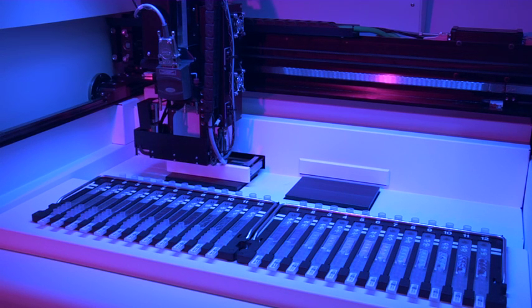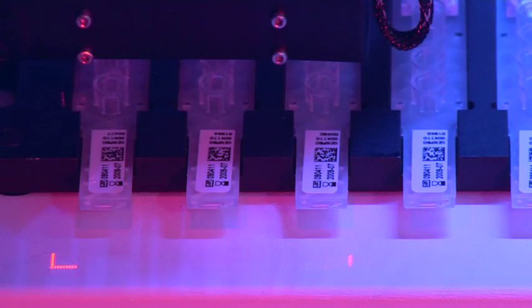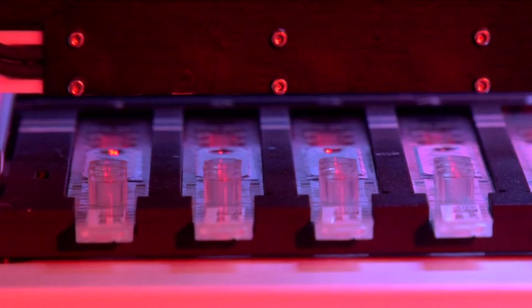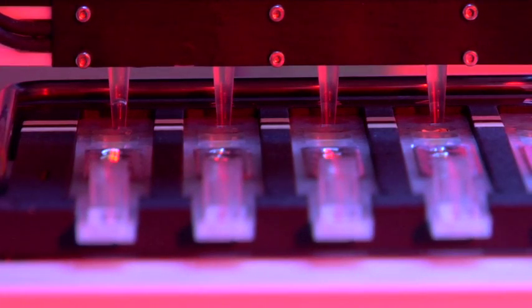As automated processing begins, the system catalogs all loaded sample prep tubes, reagent strips, and PCR cartridges. Lysis and extraction are accomplished by a combination of enzymatic action and heat, all performed in the same tube within the reagent strip.